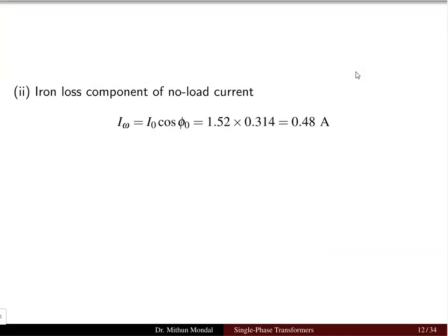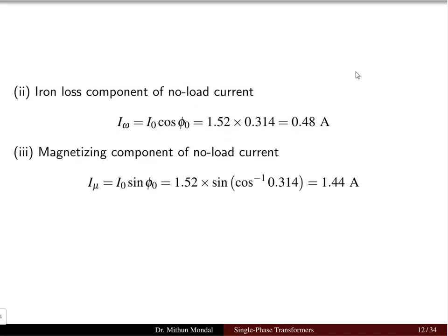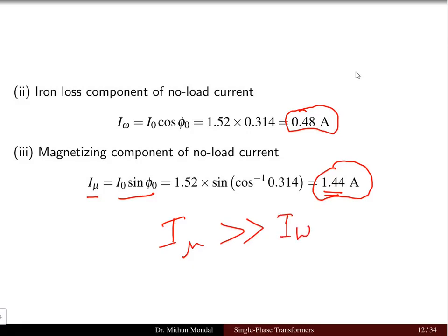Now the iron loss component of the no load current is IW, which is equal to I naught cos phi naught. We know all data, so it will be 0.48 ampere. And the magnetizing component I mu will be equal to I naught sin phi naught, which comes to be 1.44 amps. Now just have a conclusion that the iron loss component of the current is much less compared to the magnetizing component. You will always have the magnetizing component very high compared to the iron loss component. Here, on average, it is 3 to 3.5 times more. That is the magnetizing component, because the current I mu is responsible for the production of the flux in the core, and IW is only a representation of the core loss.